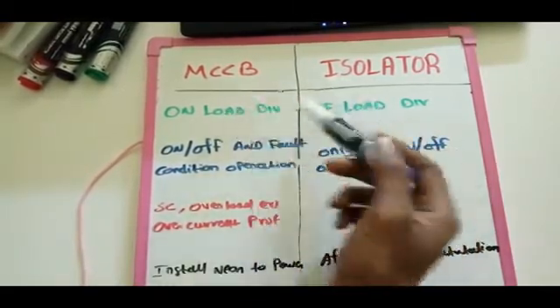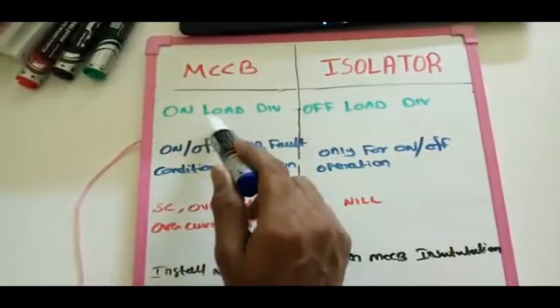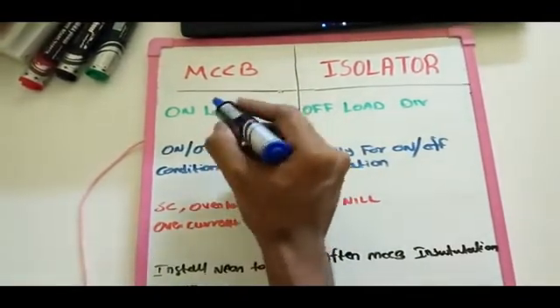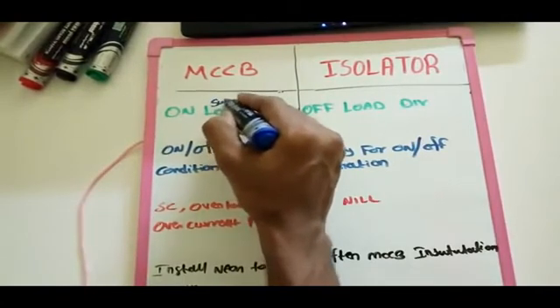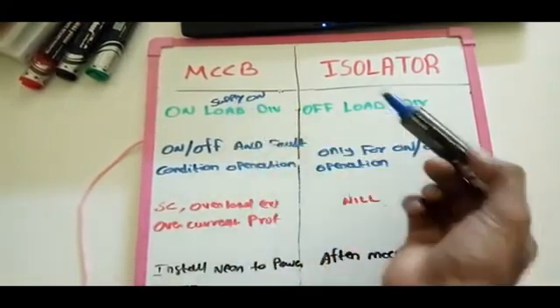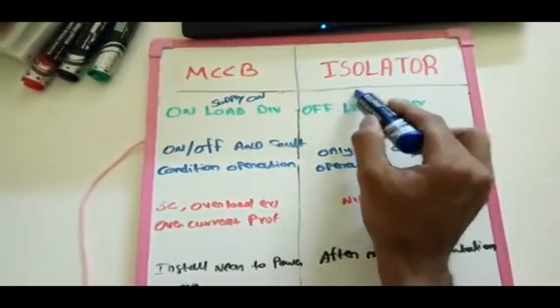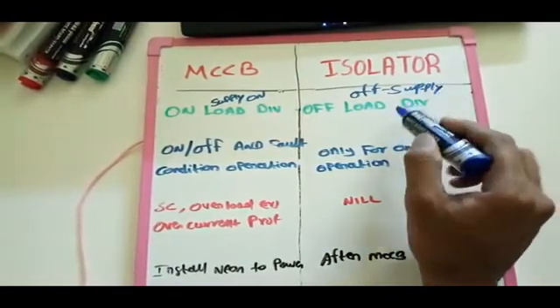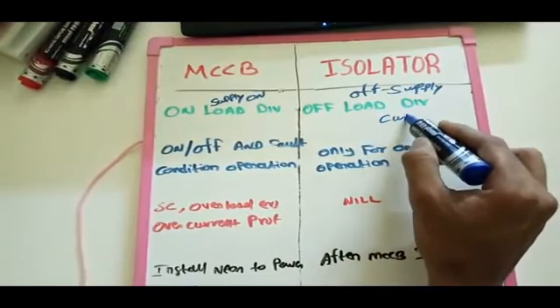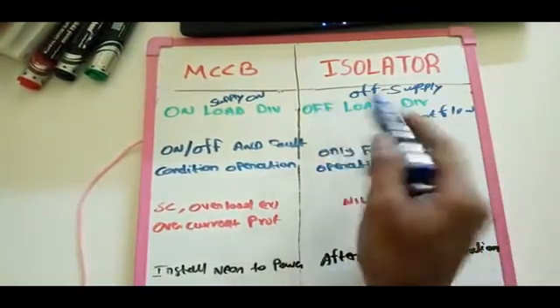The MCCB operates as an on-load device and the Isolator acts as an off-load device. The MCCB trips the circuit while the load is connected — providing overload and overcurrent protection — automatically operating to disconnect the circuit. The Isolator is used to switch off the circuit for maintenance and repair purposes, isolating the healthy main circuit to perform any maintenance or fault clearance services.